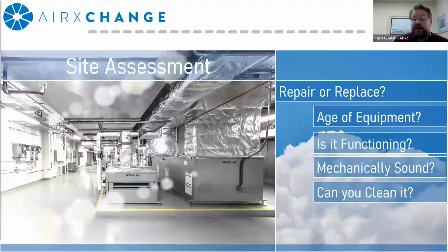Is the device functioning? And I like to point out that just because the device is spinning doesn't necessarily mean it's functioning. So you have to make sure that you're achieving your desired ventilation airflow, that you're maintaining the pressure drop that's set by the manufacturer, as well as the overall effectiveness that the device should be working at.